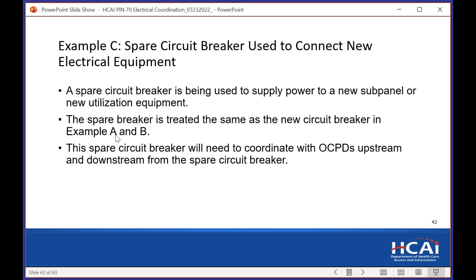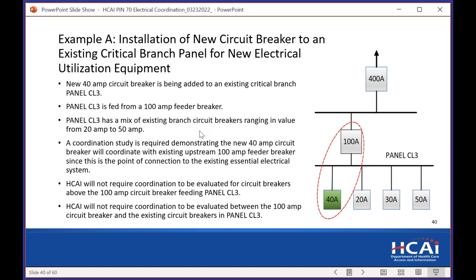So in example A, if this 40 amp was a spare 40 amp breaker in this panel, we're going to need to see coordination of that because you're adding new equipment. And so the new equipment needs to meet current code.